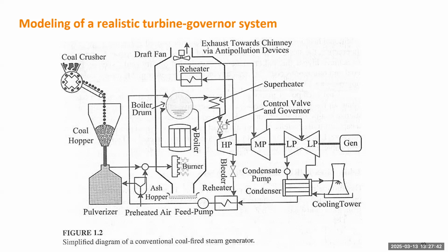But anyway, the boiler will generate high pressure, high temperature steam, which goes through the high pressure turbine. It will drive this turbine. The shaft will speed up to generate the speed for the rotor. When the high pressure steam leaves the high pressure turbine, we want to reuse the energy carried by the steam. So it goes through the reheater and comes back to a medium pressure turbine. So we can utilize that energy, and we can add another link, which is the low pressure turbine.